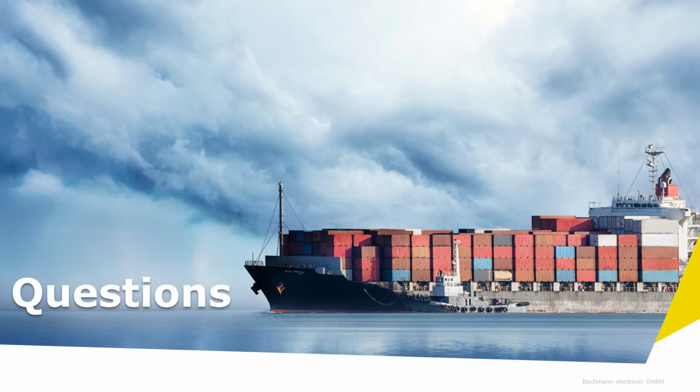It could be a pressure, it could be temperature, and it will trigger the system to take an extra measurement, so it's got more data about what's going on, and it will generate an alarm that the crew can see. Okay, so that's already in place also and working on other applications. Yeah. That's one of the advantages of being built into a control system. There's a lot of opportunities to do that sort of thing.